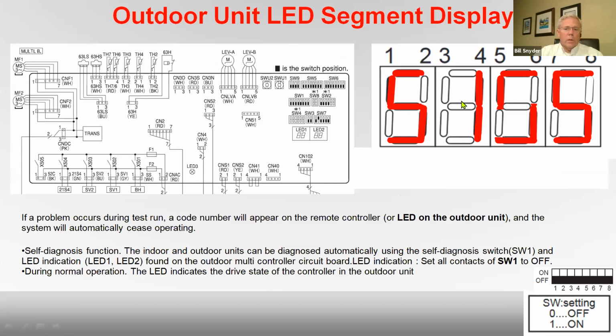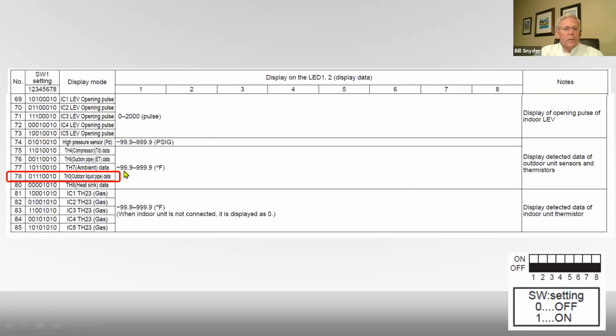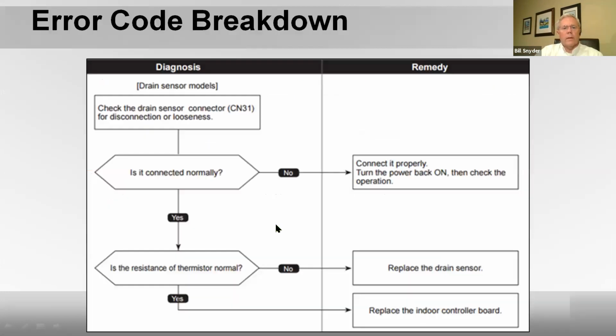And if the thermistor was good, it would actually tell you the temperature the thermistor was seeing. If it's bad, it's going to read either negative 99.9 or 999.9. So that's either shorted or open if it reads one of those two. If it actually reads a temperature, it could tell you it's 75. If it's outside air and it's 75 degrees and the unit's not running, that would be okay. So it's kind of neat. You can use that. You also have the error code breakdown, which will steer you in the right direction.